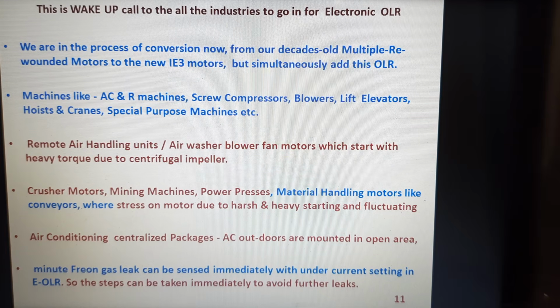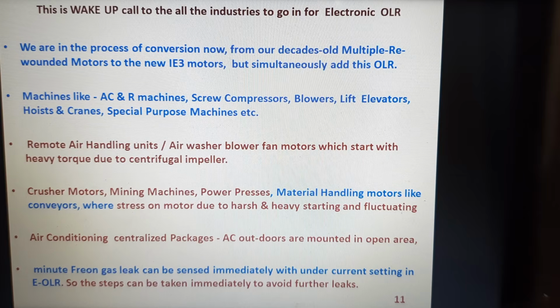Machines like AC and R machines, screw compressors, blowers, lift elevators, hoists and cranes, or special purpose machines definitely need this type of electronic OLR. Even remote air handling units or air washer blower fan motors, which start with a heavy torque during the centrifugal impeller operation, also need the electronic overload relay to protect the motor from burnout. The crusher motors, mining machine motors, power presses, and material handling motors like conveyors, where the stress on the motor is very high during static starting as well as during heavy material loading, with harsh and heavy starting and fluctuating loads, this electronic overload relay definitely protects your motor.